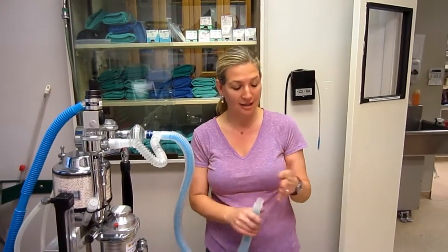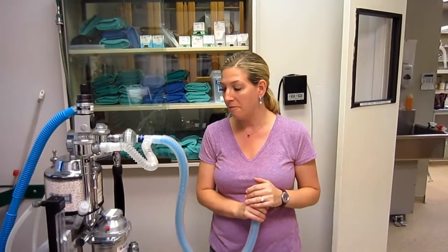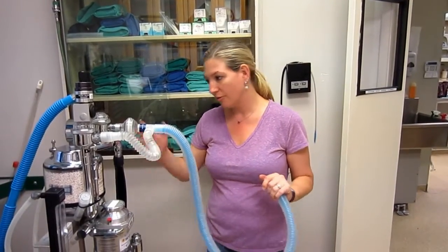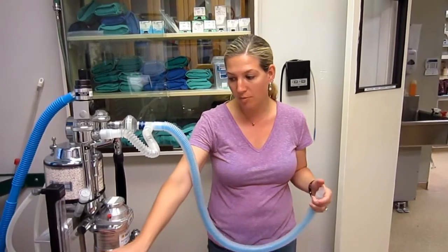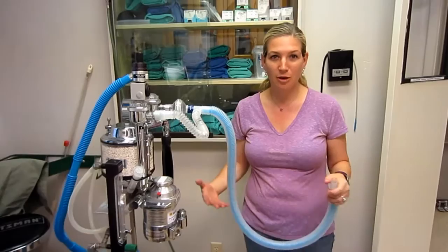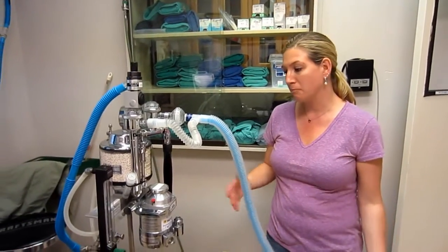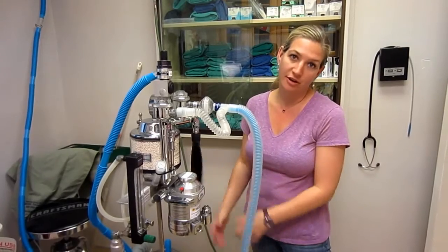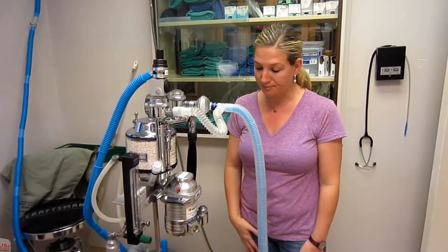But if and when you do that, you would have your patient disconnected and you would likely be blocking the tube with your hand. It is far too great of a pressure to deliver directly to your patient. So you never want to press this when the patient is connected. You would usually do this as a pressure check or to quickly get oxygen to try to flush their lungs.